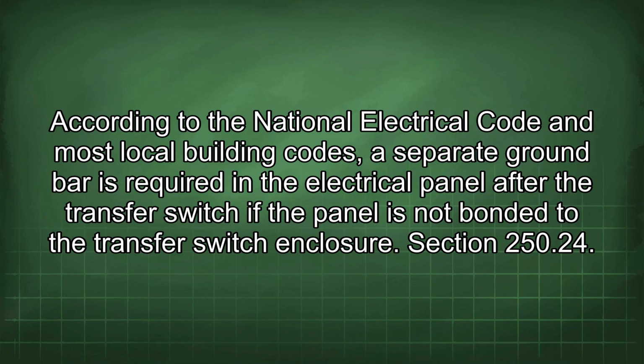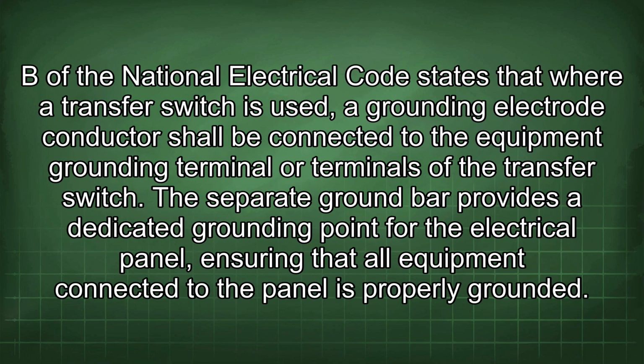According to the National Electrical Code and most local building codes, a separate ground bar is required in the electrical panel after the transfer switch if the panel is not bonded to the transfer switch enclosure. Section 250.24(B) of the National Electrical Code states that where a transfer switch is used, a grounding electrode conductor shall be connected to the equipment grounding terminal or terminals of the transfer switch.